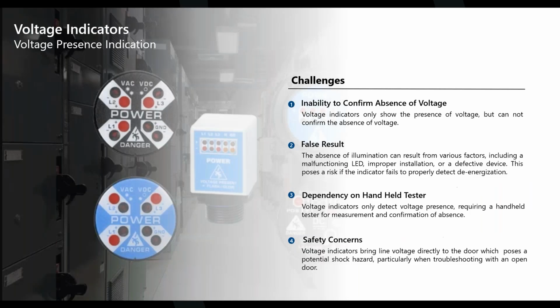Voltage indicators are useful for showing if electricity is present, but they have some limitations and safety concerns. They cannot confirm the voltage is completely absent, which is critical for safe work. Sometimes the light may give a false reading due to issues like faulty LEDs, incorrect installation, or device failure. These indicators also require a separate handheld tester to measure voltage and verify the power is off. Additionally, because they bring the line voltage to the panel door, they can pose a shock hazard, especially when troubleshooting with the open door.